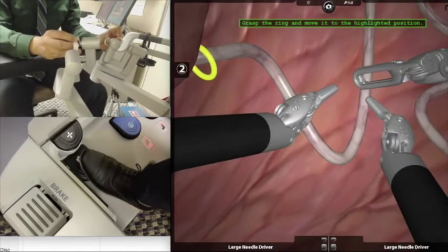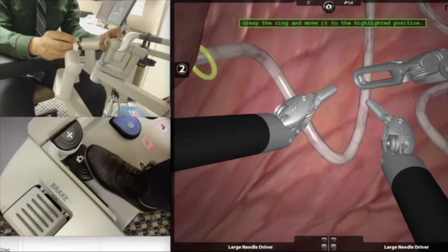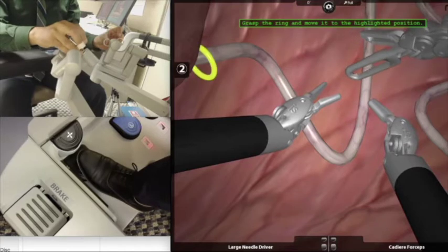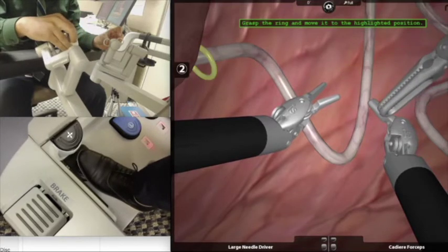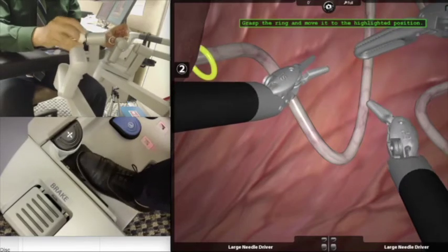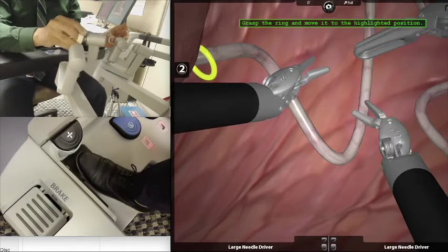This exercise has an extra third retracting arm, which we call the fourth arm. This is activated by the side foot pedal, as shown here. On activating the fourth arm, arm number one on the right side freezes up, and now your master controls control arm number two and the third arm. You can toggle back and take control of arm number one again.